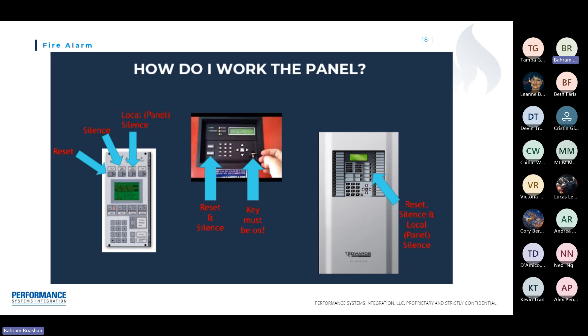First, silence the fire alarm control panel by pressing silence. Then press reset. This will cause the panel to send voltage to check that each input device is having continuity. If it does, the panel will reset. If it does not, the panel will show a trouble. If you see a trouble, write down what that trouble is on the display and then call PSI Technical for service.